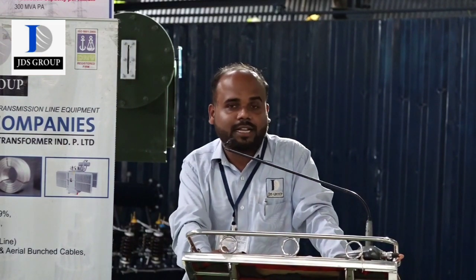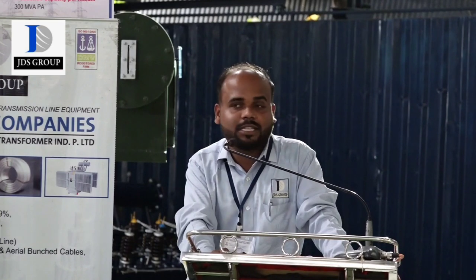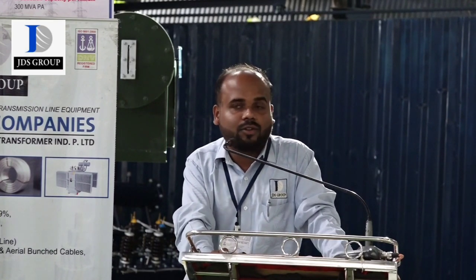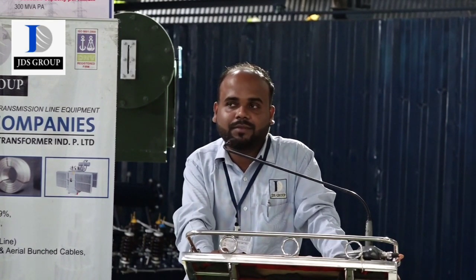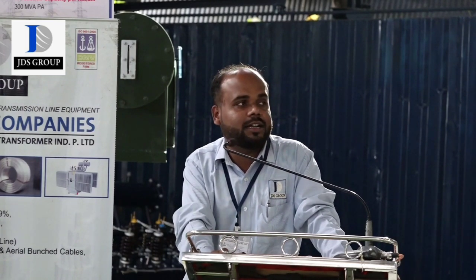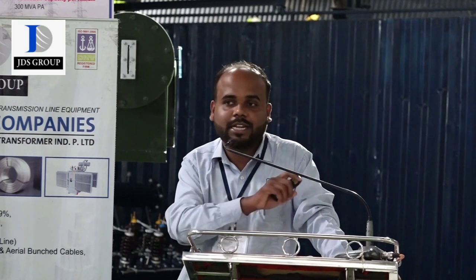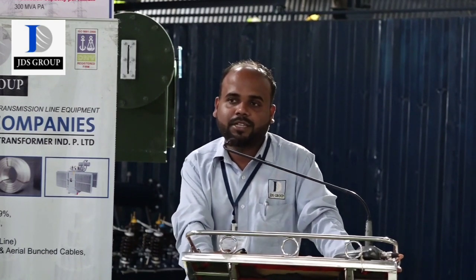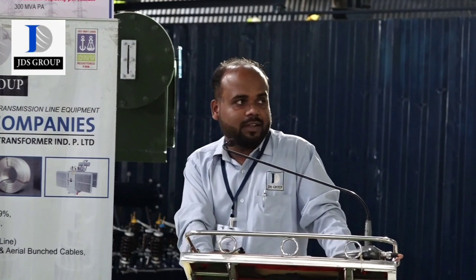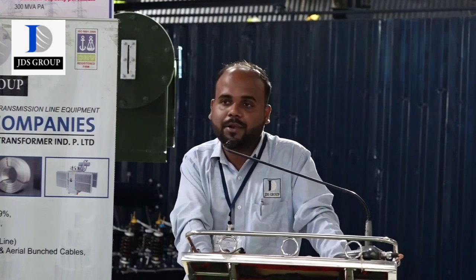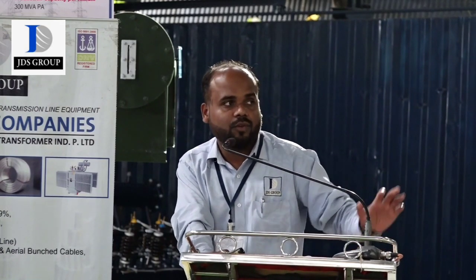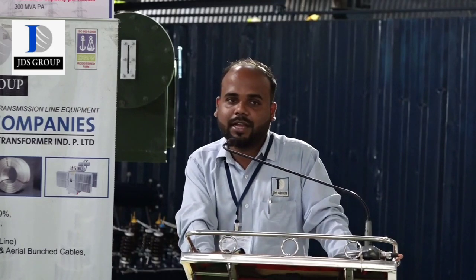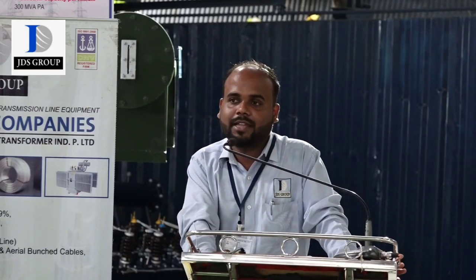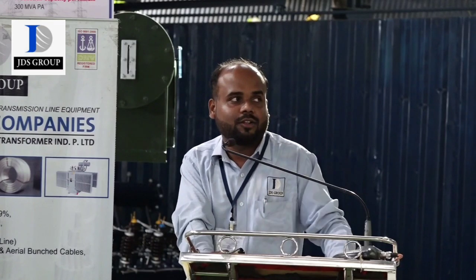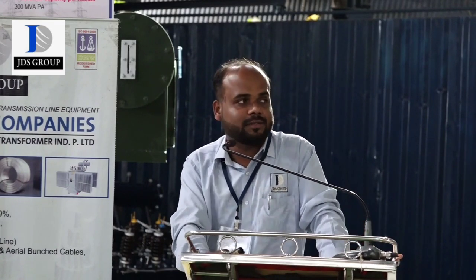After the core losses, the next test is the measurement of load loss. The load loss is also known as the short circuit test, in which we apply the rated current on the HV side. Our HV side rated voltage is 11 kV and the LV side is short circuited. For example, if you take a 100 kVA transformer, the HV side current is 5.25 ampere. So we allow 5.25 ampere to flow on the HV side of the transformer. By this we calculate the total load loss in the transformer.